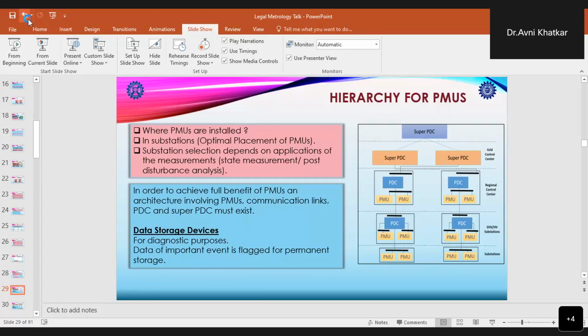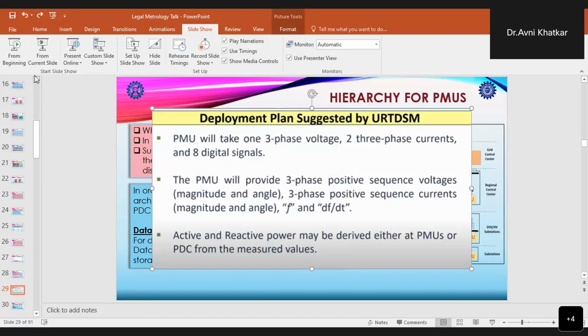So as per the deployment plan strategy of URTDSM, PMUs were to be installed. They will take one three-phase voltage, two three-phase currents, and 8 digital signals. And then these PMUs will provide three-phase positive sequence voltages, that is both magnitude and angle, and three-phase positive sequence currents, both magnitude and angle, the frequency and change of frequency. And the active and reactive power may be derived either at the PMUs or at the PDCs from the measured values.